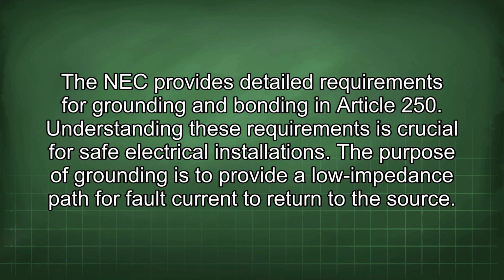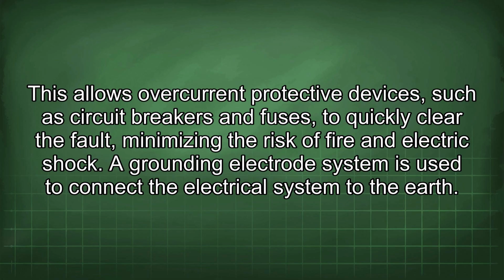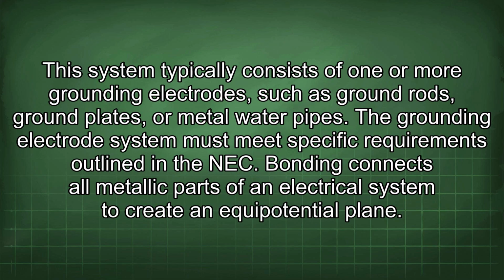The purpose of grounding is to provide a low impedance path for fault current to return to the source. This allows overcurrent protective devices, such as circuit breakers and fuses, to quickly clear the fault, minimizing the risk of fire and electric shock. A grounding electrode system is used to connect the electrical system to the earth. This system typically consists of one or more grounding electrodes, such as ground rods, ground plates, or metal water pipes. The grounding electrode system must meet specific requirements outlined in the NEC.